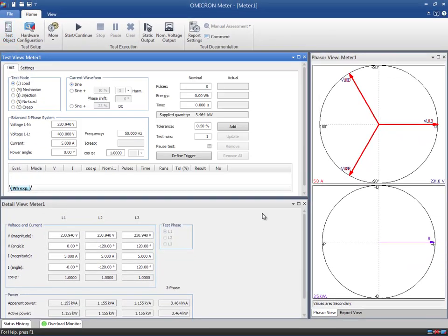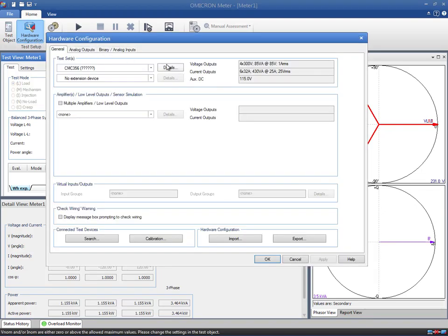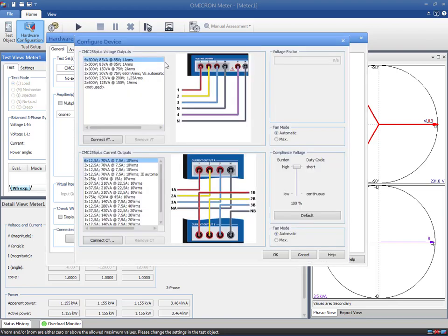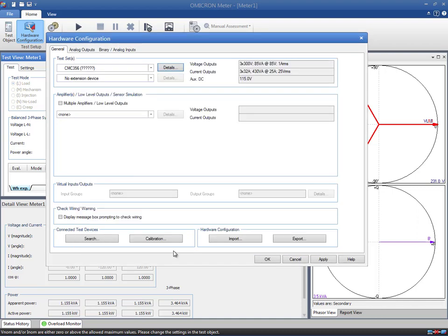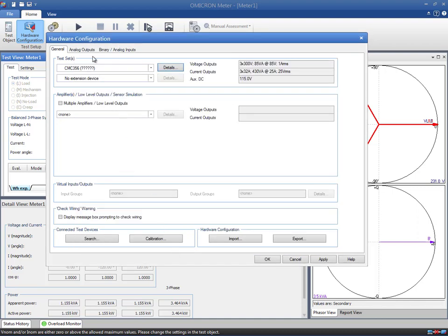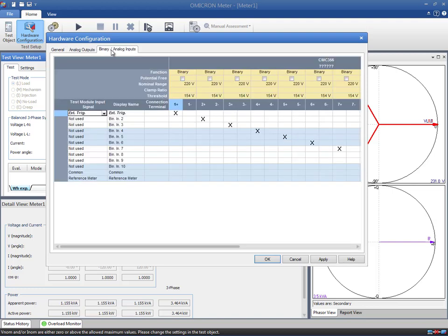The next step is the hardware configuration. We will choose to have three voltage outputs and three current outputs from the general configuration of the CMC test set. This particular meter includes binary outputs in addition to LEDs. This means that there is no need to use an optical scanning head since we can route one of the relay's outputs to one of the CMC's binary inputs. Therefore, we configured the first input to be a counter and confirmed the dialog.